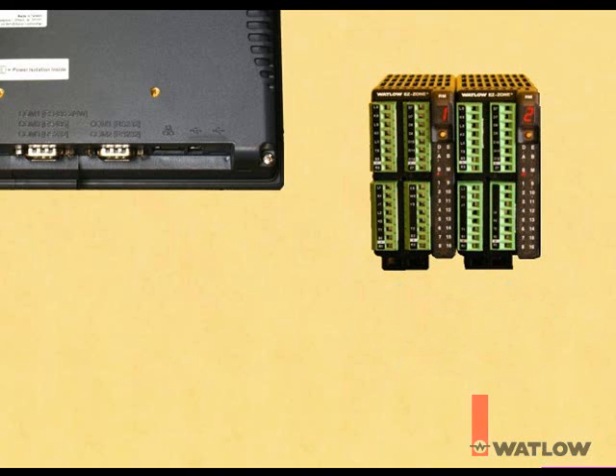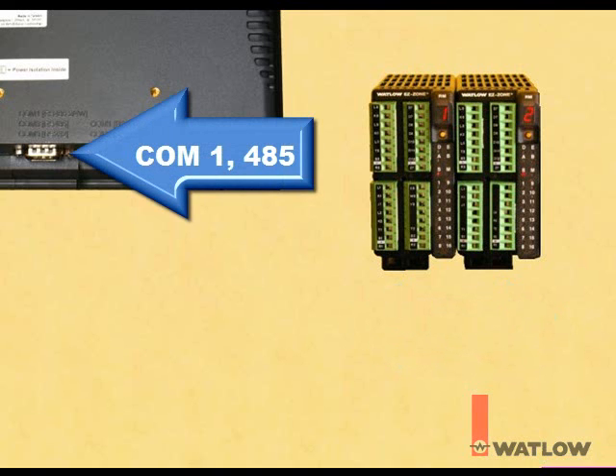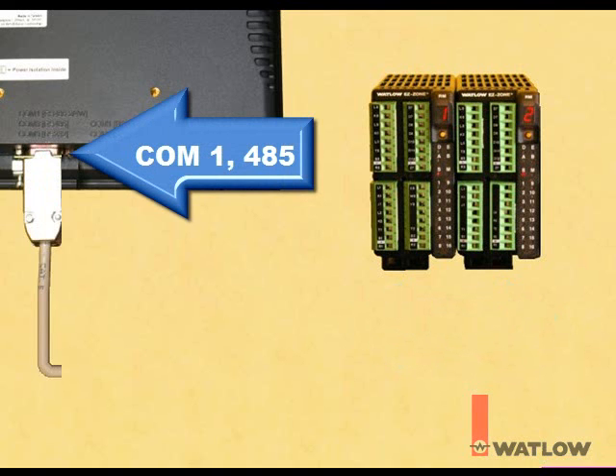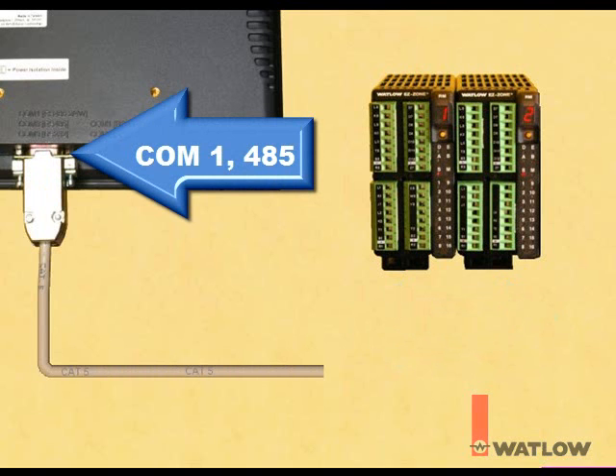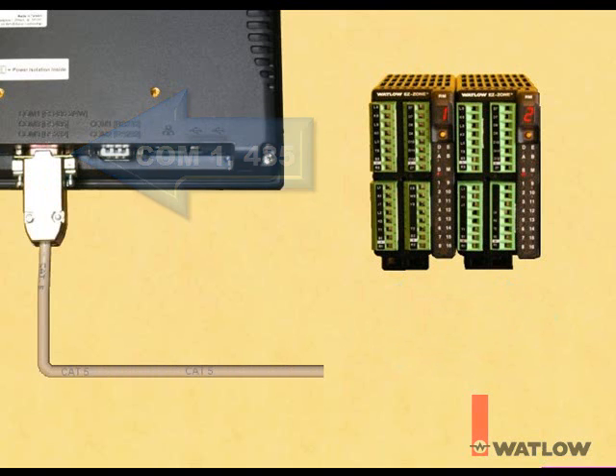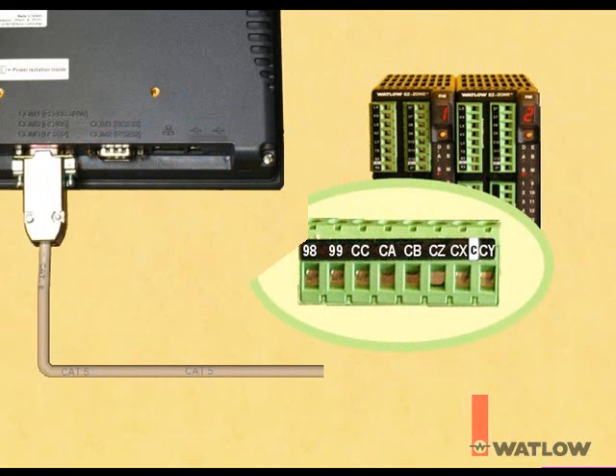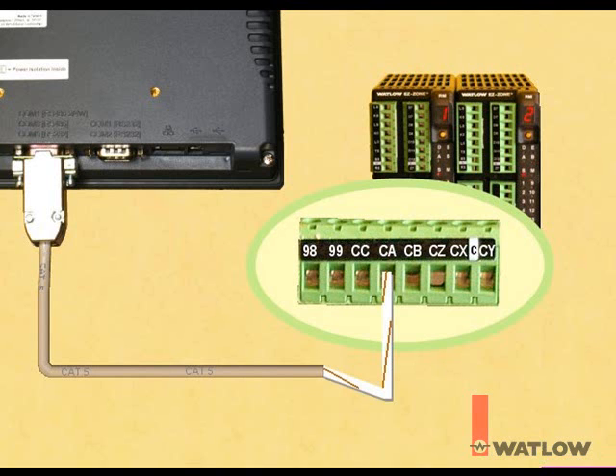Connect the DB9 end of the OIT communications cable available from Watlow to the COM1-485 connector on the OIT. Connect the wires at the other end of the cable to the screw terminals at the bottom of the first RM control module. Connect the white with brown stripe wire to the terminal labeled CA, the blue wire to CC, and the brown wire to CB.